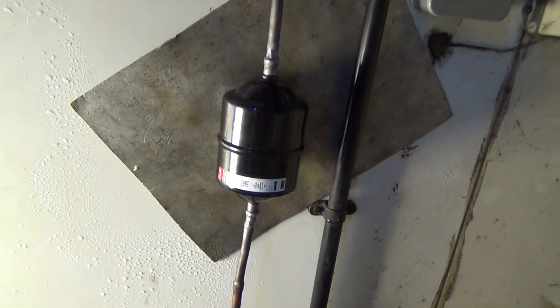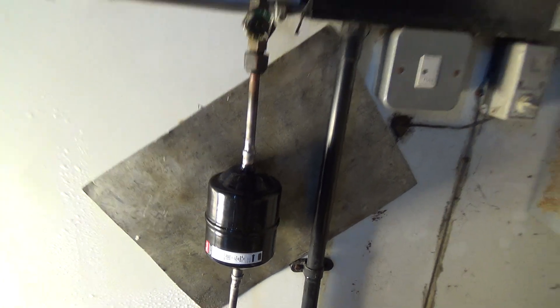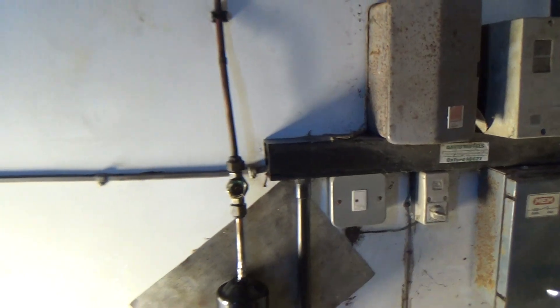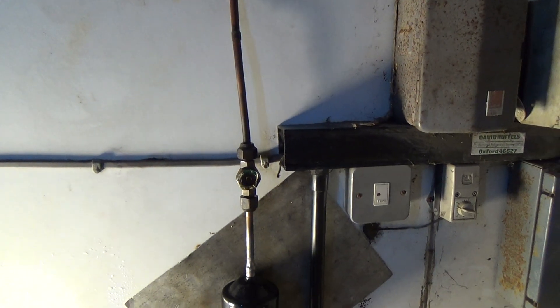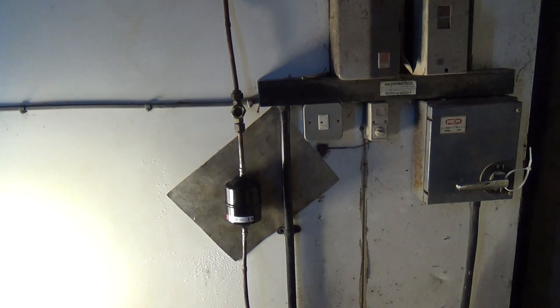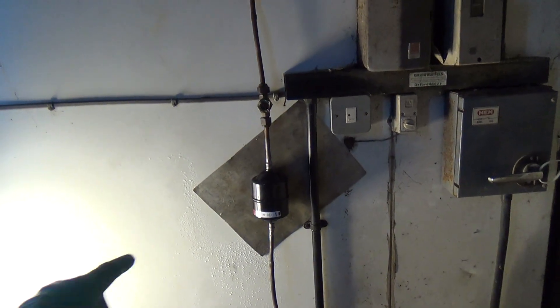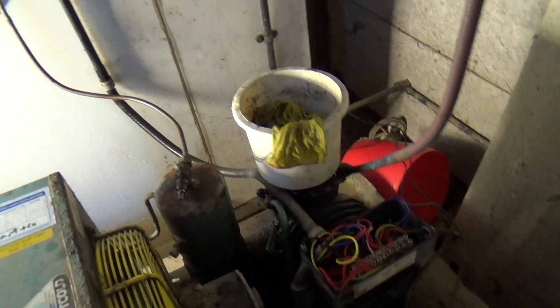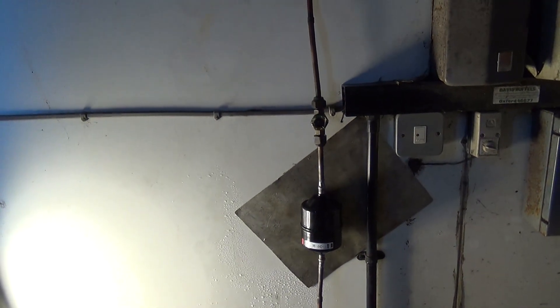That's a new dryer in there. Might leave that. I don't think it's got any moisture issues in there. It's got to get a whole new refrigerant, fresh dryer and oil in the compressor. So that should be OK.